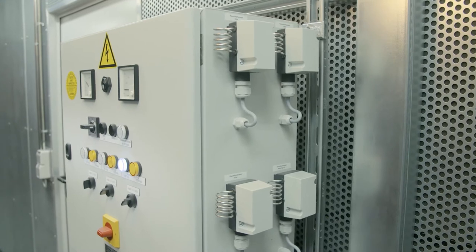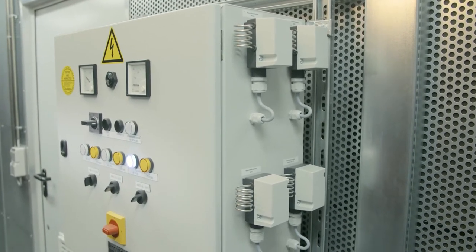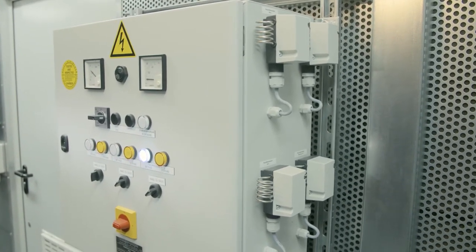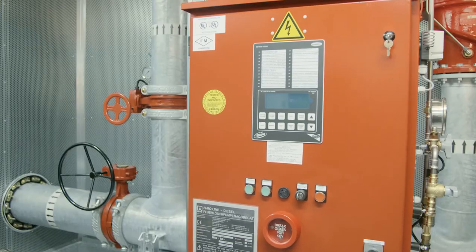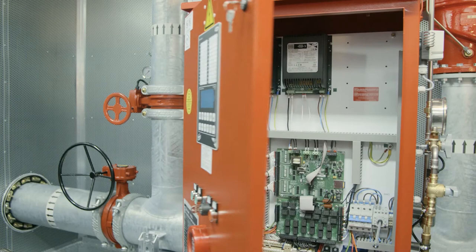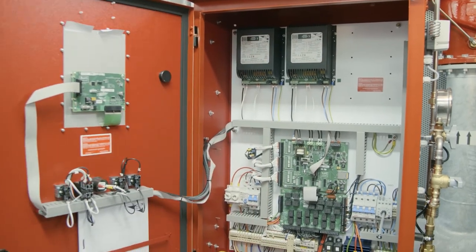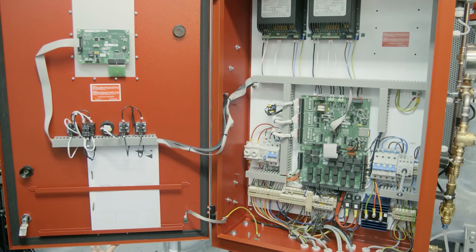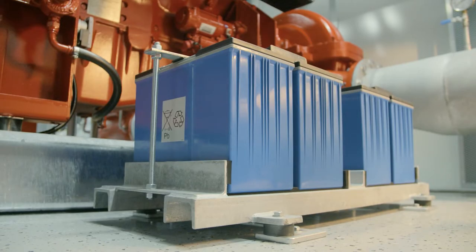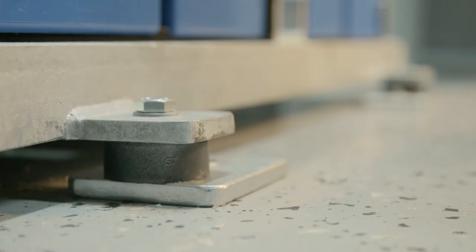All heating and ventilation components inside the station are controlled by IP54 industrial room thermostats. The FM/UL-approved controller with manual testing device is parameterized, factory tested, and installed ready for operation. Redundant, maintenance-free starter batteries ensure safe engine start-up under any conceivable conditions.